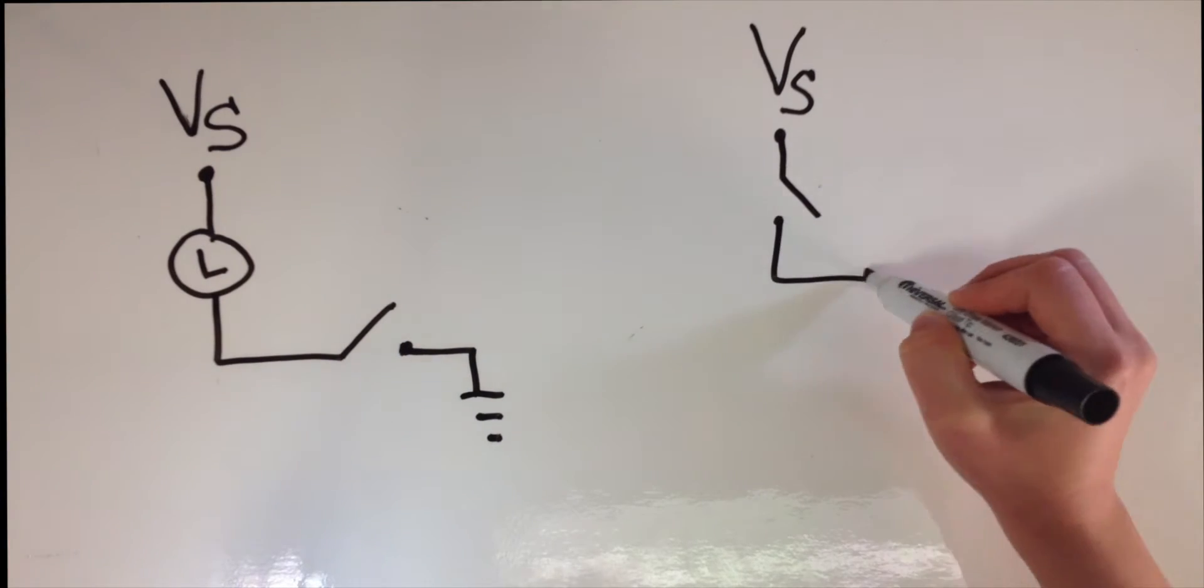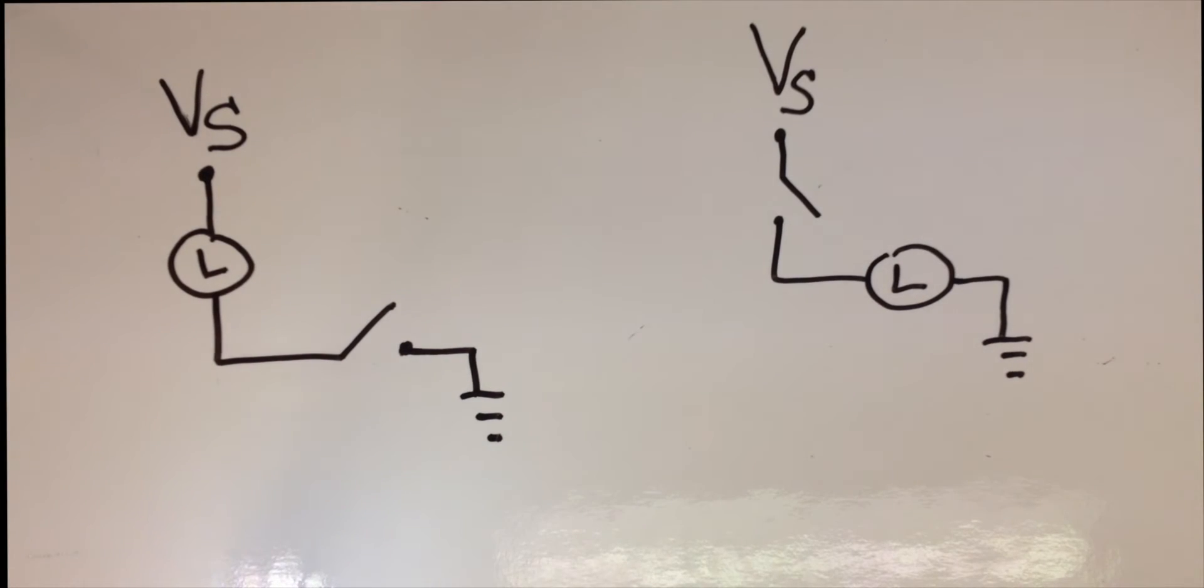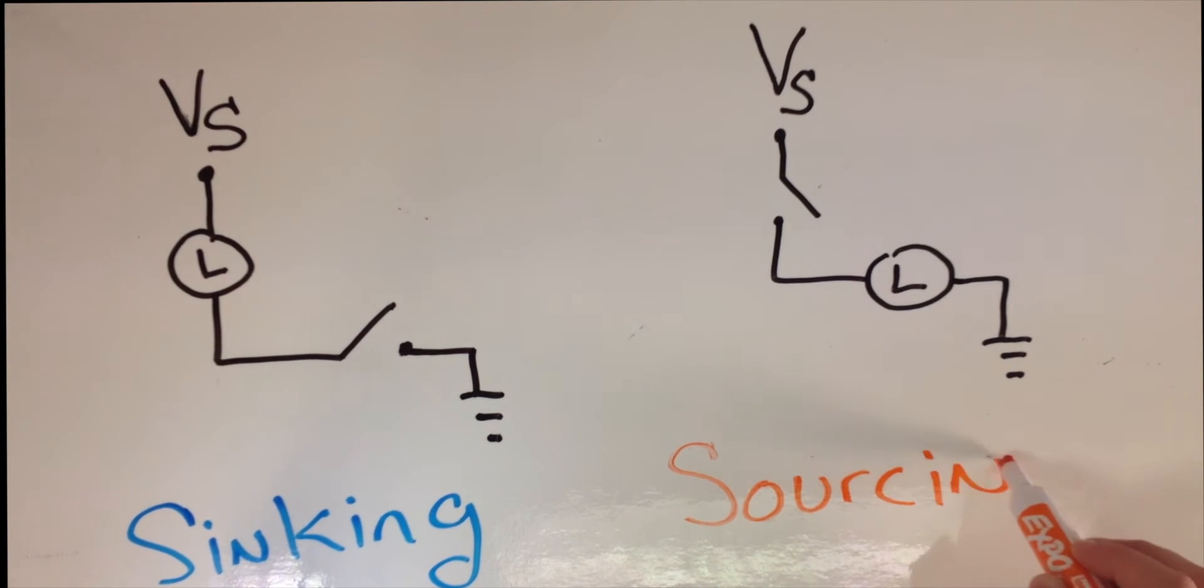Here is a simplified wiring diagram of the sinking and sourcing options of the opto-isolated outputs. In sinking or low side configuration, the switch is placed between the load and ground. In sourcing or high side configuration, the switch is placed between the voltage supply and the load.